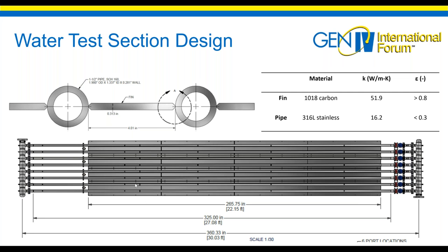The water test section design is shown here. We're using stainless steel for the water riser tubes, which are welded to carbon fins that receive the radiation heat transfer and conduct it to the water. The fins are made of 1018 carbon steel because it has a high emissivity, which is good for the radiation heat transfer process. However, in reactor systems you want to keep the water clean, and the stainless steel provides the ability to keep the water clean while maintaining the good heat transfer processes that the carbon steel provides.